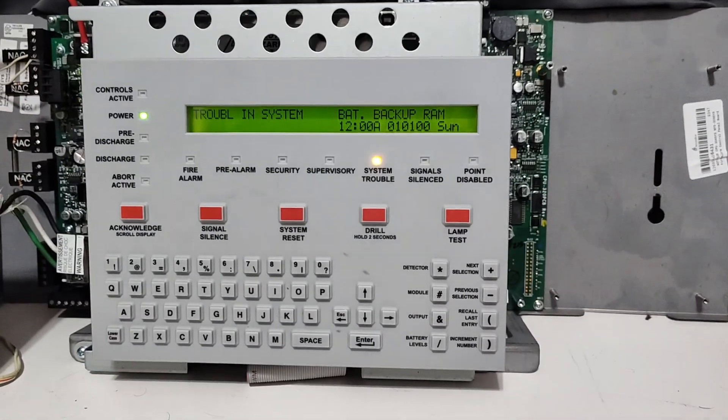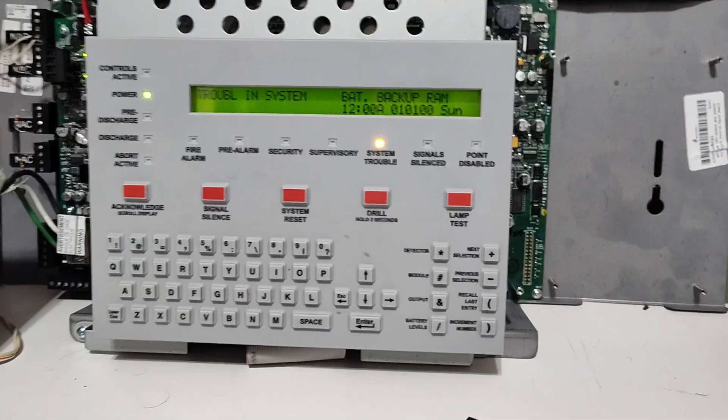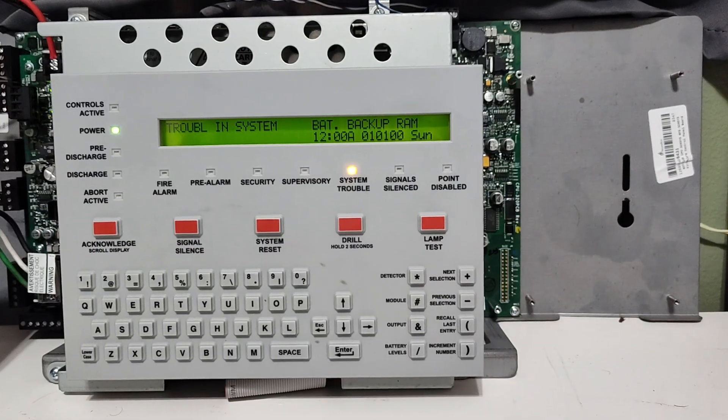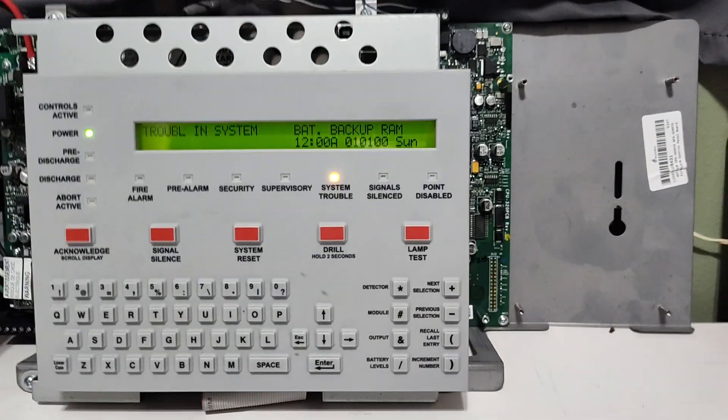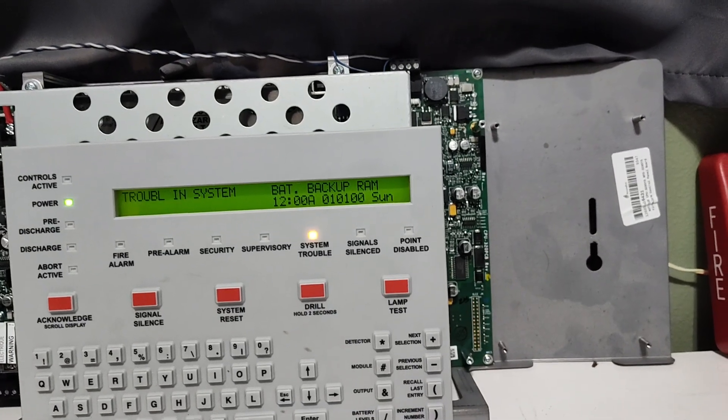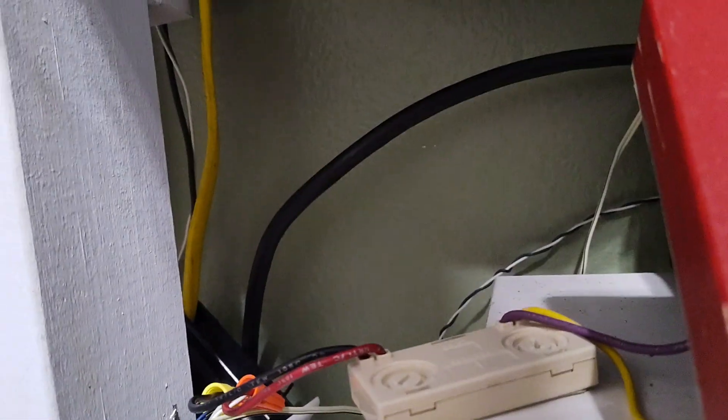Until then, I will be having a backup battery RAM trouble, and hopefully the power doesn't go out long enough for the batteries to die. On the system today, we have a CLIP system going on here. That's simply because all of my FlashScan devices aren't currently on the NFS2-640. I don't feel like changing everything out just so I can borrow a CLIP pull station.